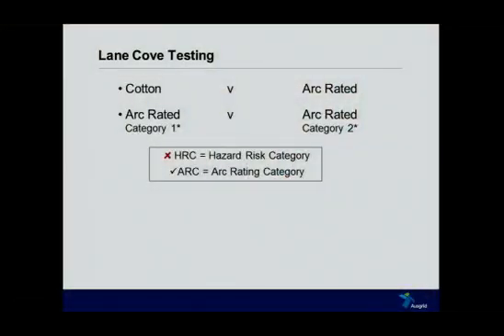We had a divergence of opinion within the supply industry. Some said nothing wrong with cotton, it served us well in the past, let's stick with cotton. Others said we must go with arc-rated clothing, category 2 minimum, 8 calories, we can't consider anything less. So we put both extremes to the test, comparing cotton with arc-rated, and category 1 with category 2. The categories used to be called HRC, hazard risk categories, now changed to ARC, arc rating categories.